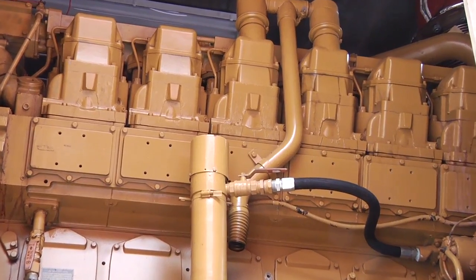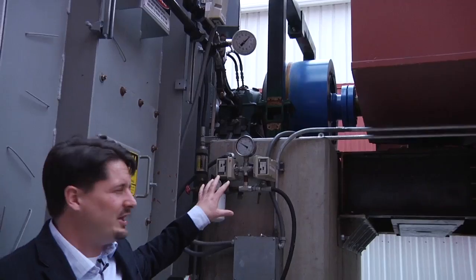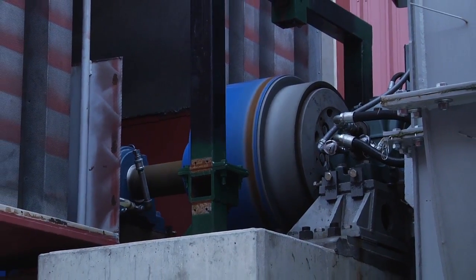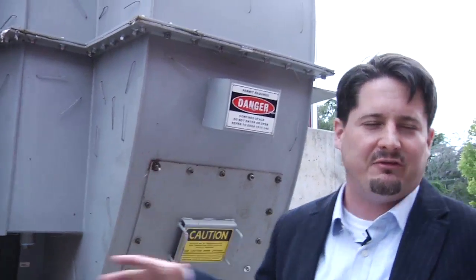Power is delivered to the fan assembly by this 1,800 horsepower diesel engine. This engine came out of a generator set — it's not a traditional application. Originally we looked at using electricity, but it was so expensive that we decided to go with the engine. It's actually direct coupled into the fan assembly over here. You can see the drive train. That part that's spinning is the air clutch — that's actually how we couple the power right through here. The engine's off and it's still spinning. Once we disconnect all the power system, it takes a few minutes for the fan to stop spinning.